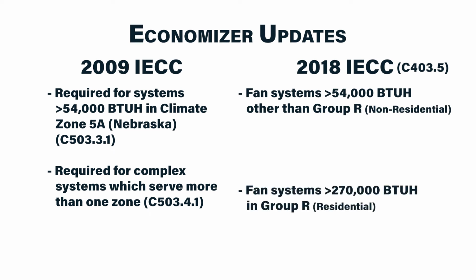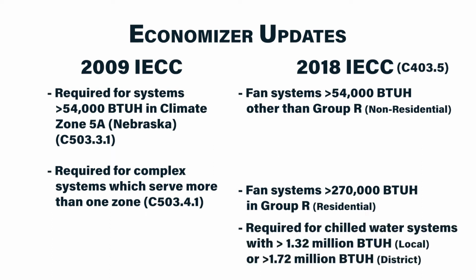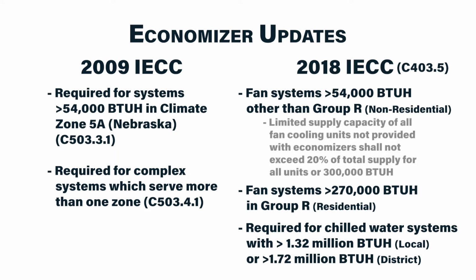Residential buildings have a little bit more leeway, and an economizer is only required for fan systems that are greater than 270,000 BTUH, or about 22.5 tons. Water-side economizers are also required for large chilled water plants that are over 1.3 million BTUH and don't have systems on it that use air-side economizers. In addition, there's a new requirement that all fan cooling units not provided with economizers shall not exceed 20% of the total supply air for all units, or 300,000 BTUH, whichever is greater.